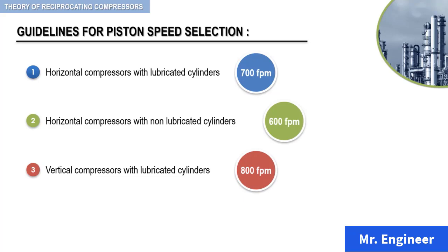And finally, for vertical compressors with non-lubricated cylinders, here again, a lower speed must be considered. 700 feet per minute is an acceptable guideline.